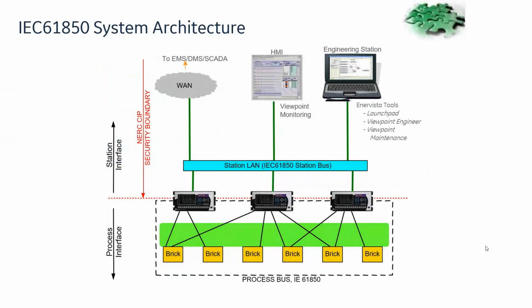Just to give you an example of a system architecture, on the top part of this, where we connect to our SCADA, is what we refer to as the station bus, where all our SCADA, metering information, maybe non-critical tripping information goes. And then we have the process bus, the interconnection from our relays to our process equipment like our breakers, transformers and such, where the data is critical, like CT, VT information we're getting from our process equipment. That's critical information that needs to get there.